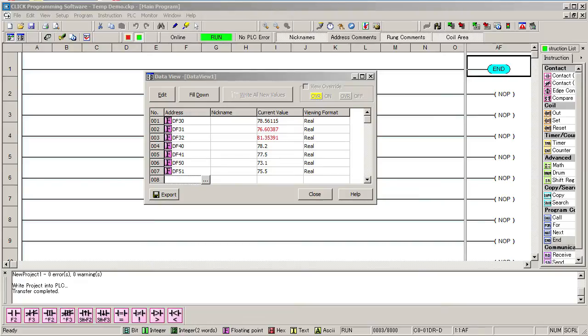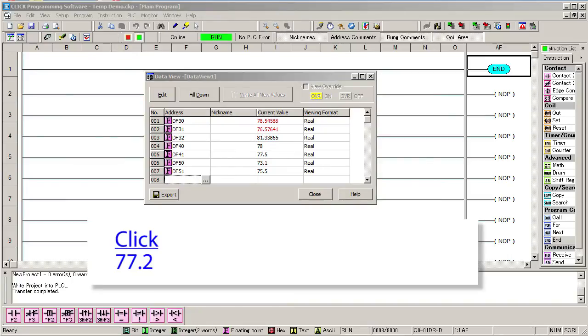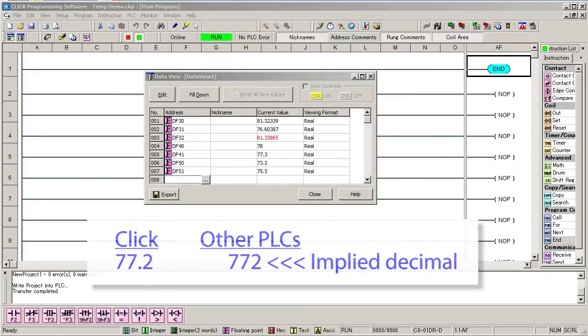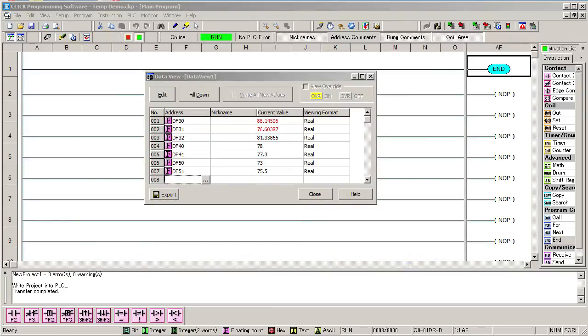Here's another key feature of the CLICK PLC. The values shown are the actual temperature values. Some PLCs give you a number with an implied decimal point, so instead of 77.2 degrees, you get 772 degrees and you have to remember that there is an implied decimal. The CLICK gives you the actual decimal temperature value.